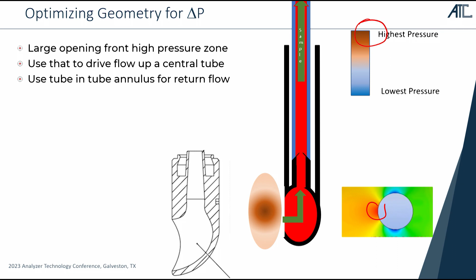At the same time as fluid is flowing and impacting on this probe, there's low pressure regions on the side. So we said over here on the sides of the tube, there's going to be a low pressure region. So we make a big set of ports on either side of the probe body, and those become our return points. Fluid that's gone up through the center region returns back through this annular region and goes out those ports and returns back into the process lines.